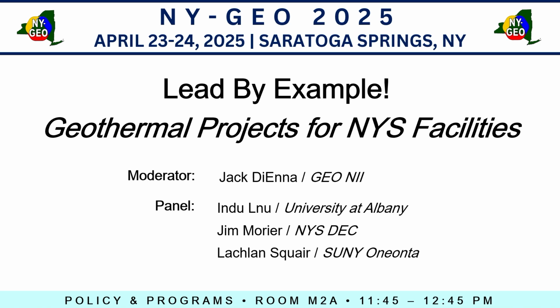Right, so for the central plant project, we're looking at both the low carbon, low GWP synthetic refrigerant, but also natural refrigerants. The Liberty Terrace domestic hot water project happening this summer is going to be a CO2 heat pump. At the central plant we're looking at CO2, but mostly ammonia and some of the synthetic low GWP options.